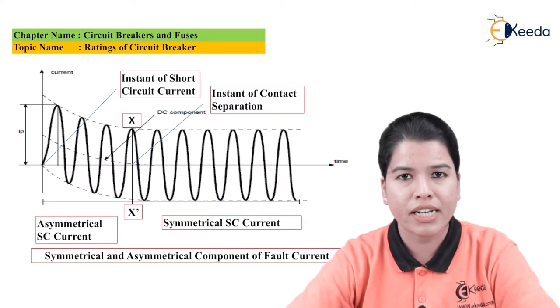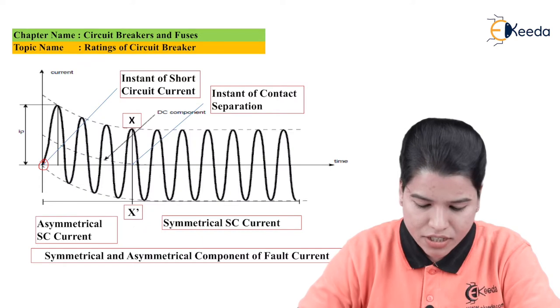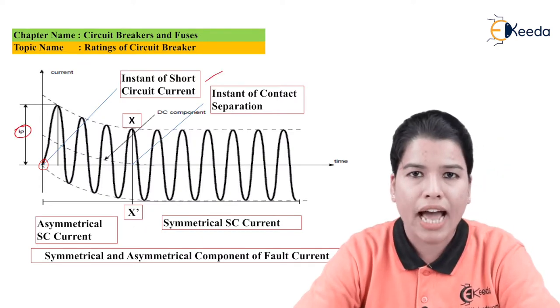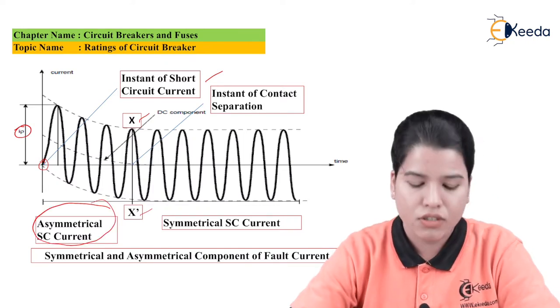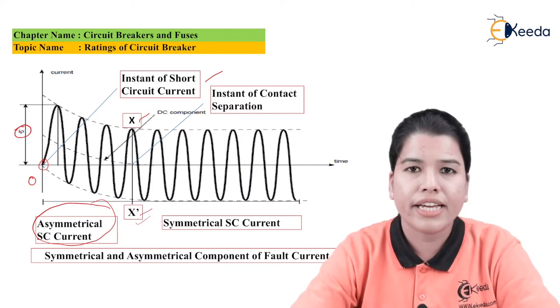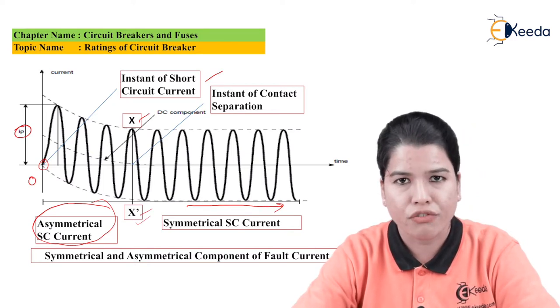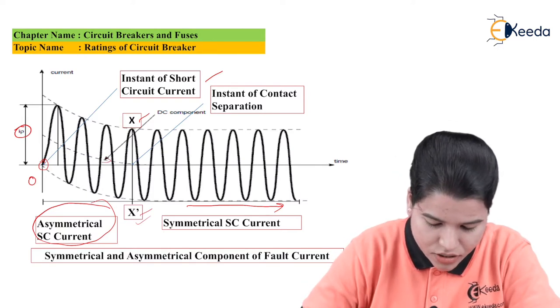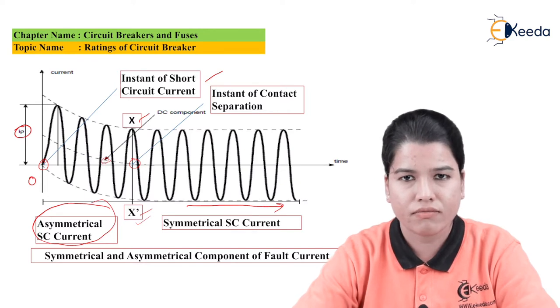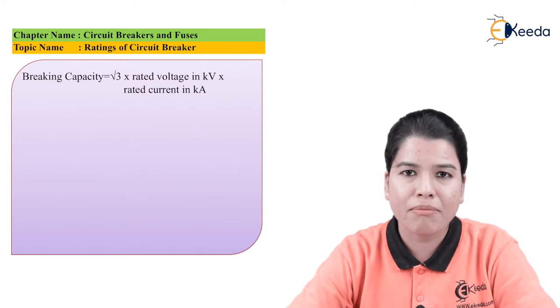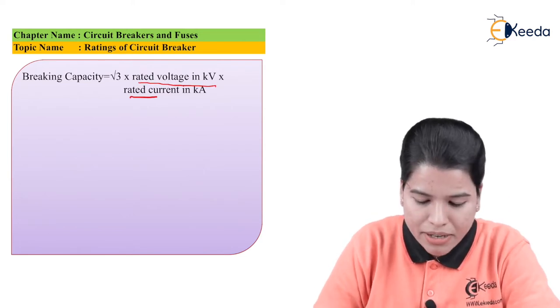On the graph of symmetrical and asymmetrical components of fault current: the point where short circuit current occurs is marked, ip is the peak value of fault current. X to X' represents the period up to which the waveform is asymmetrical; from 0 to X' is the asymmetrical component, and from X' forward it becomes the symmetrical component. The dotted line shows the DC component. The instant at which contacts separate is also marked. The formula for breaking capacity is: Breaking Capacity = √3 × rated voltage (kV) × rated current (kA).